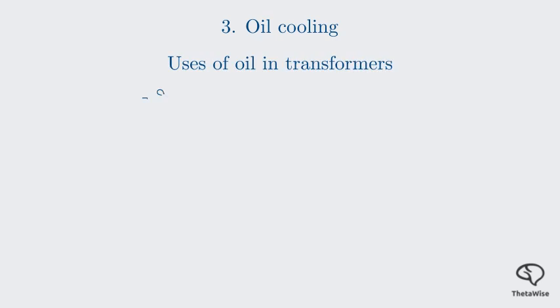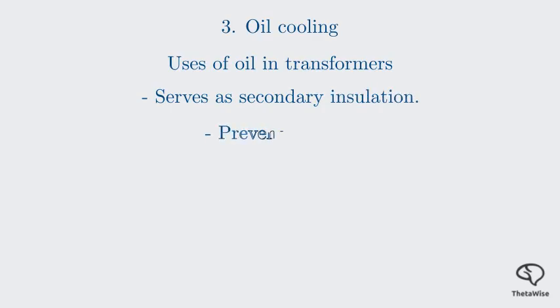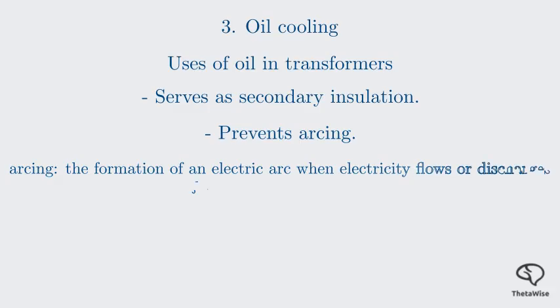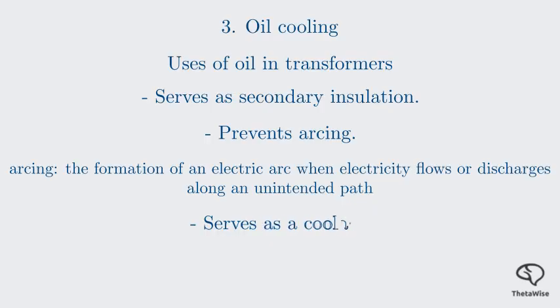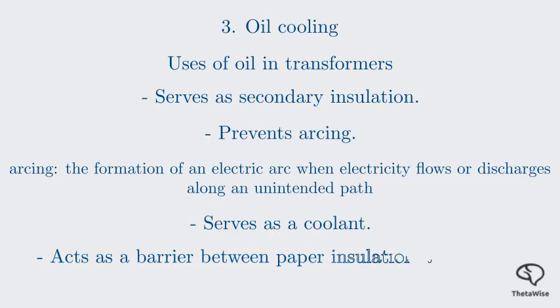Let's list them. First, it acts as a secondary insulator, adding to the insulation of the windings. Second, the oil prevents arcing. An arc is a powerful electrical discharge that can occur between high voltage points. The oil's insulating properties stop this. Let's define arcing. Arcing is the formation of an electric arc when electricity flows or discharges along an unintended path. Third, and this is its main job in cooling, the oil serves as a coolant. It absorbs the heat from the windings and the core. Fourth, it provides a barrier between the paper insulation of the windings and atmospheric oxygen. This prevents the oxygen from degrading the insulation.